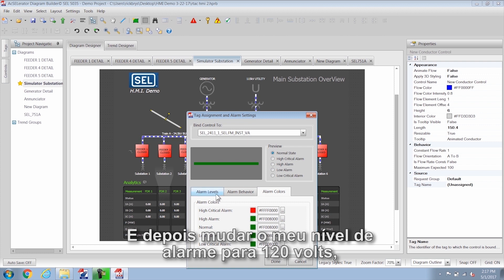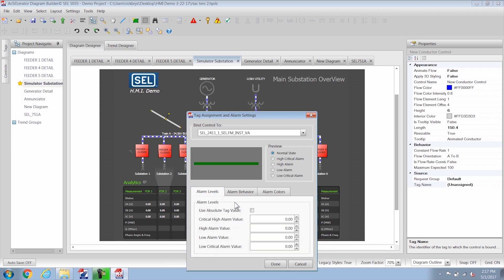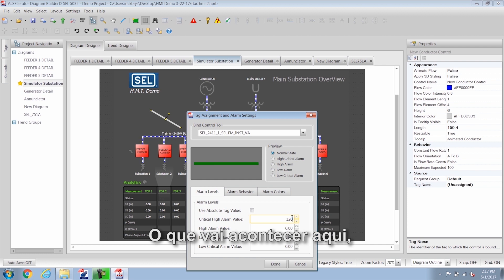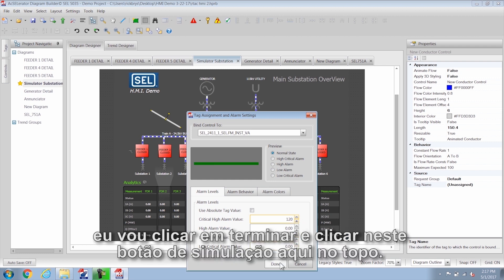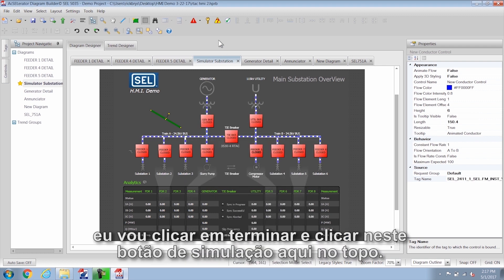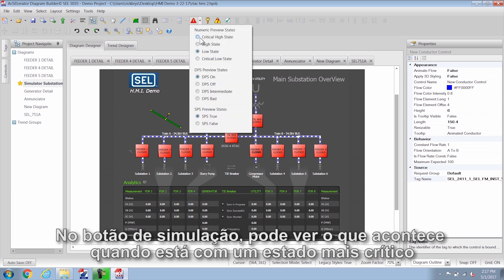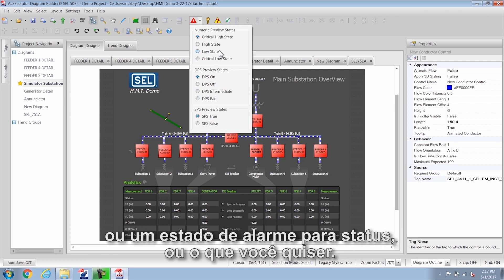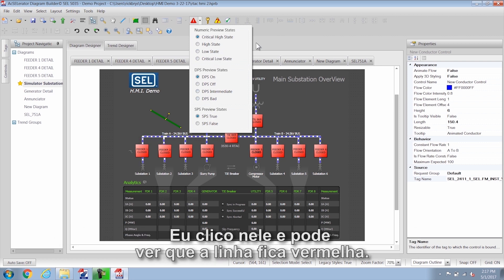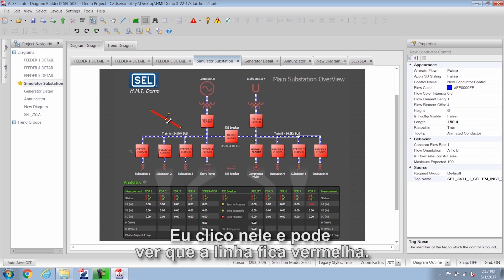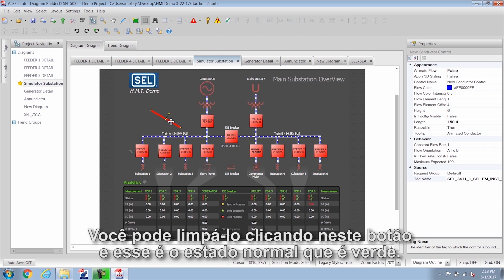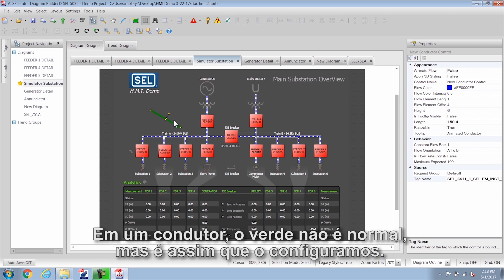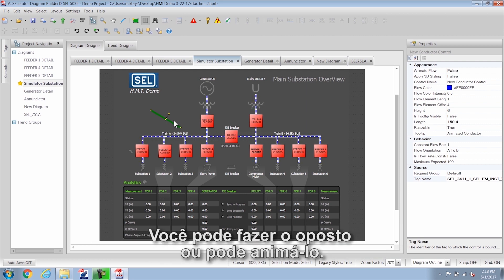I'll change the alarm level to 120 volts for the critical high. I'll click done and click on the simulation button up at the top. With the simulation button you can see what happens during a real critical high state or an alarm state for status or whatever you want. You can see that the line turns red, and clearing it shows the normal state which is green. On a conductor green is not typically normal, but that's how we set this up — you could do the opposite or have it animated.